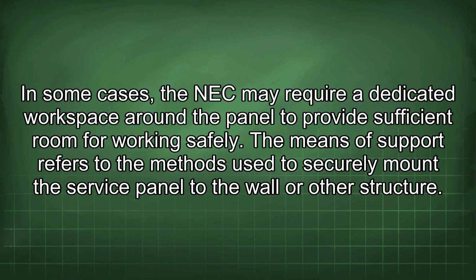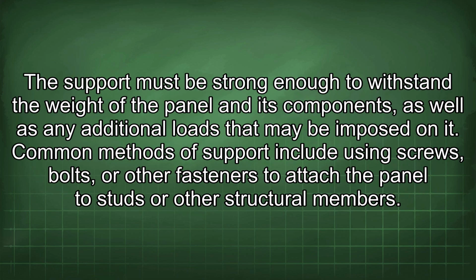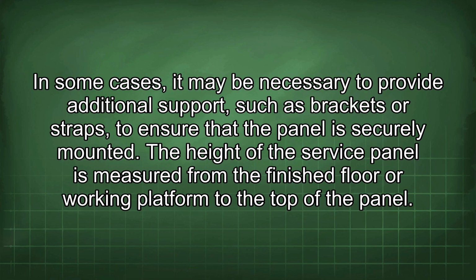The means of support refers to the methods used to securely mount the service panel to the wall or other structure. The support must be strong enough to withstand the weight of the panel and its components, as well as any additional loads that may be imposed on it. Common methods of support include using screws, bolts, or other fasteners to attach the panel to studs or other structural members. In some cases, it may be necessary to provide additional support, such as brackets or straps, to ensure that the panel is securely mounted.